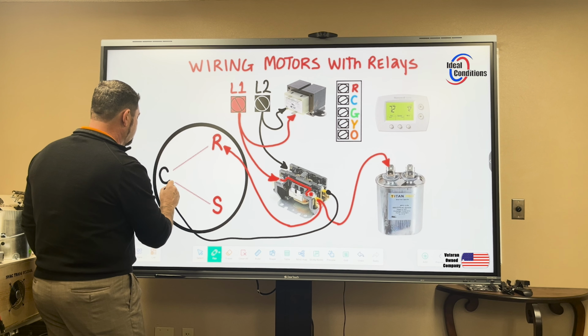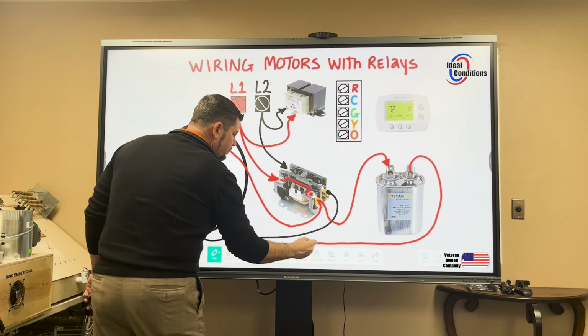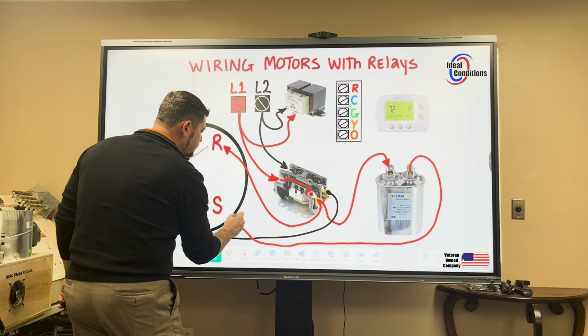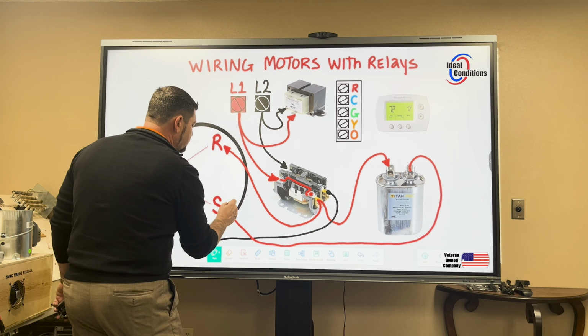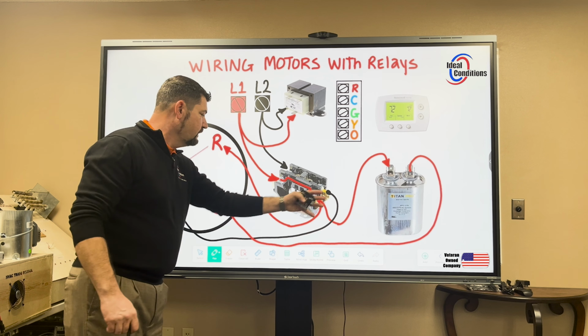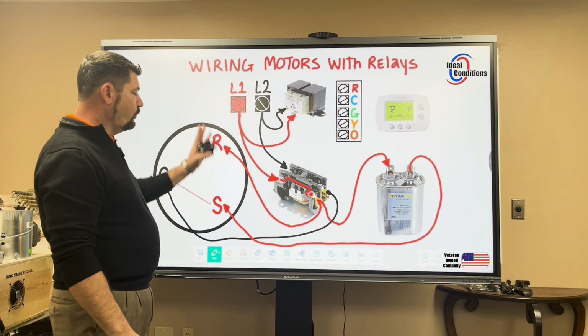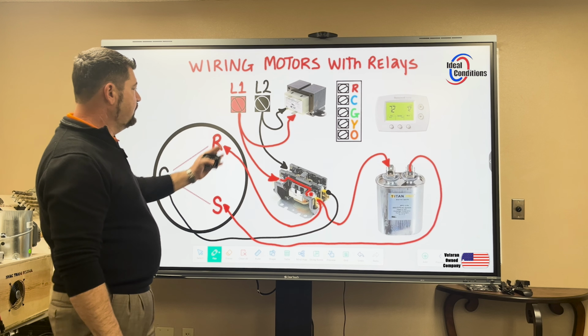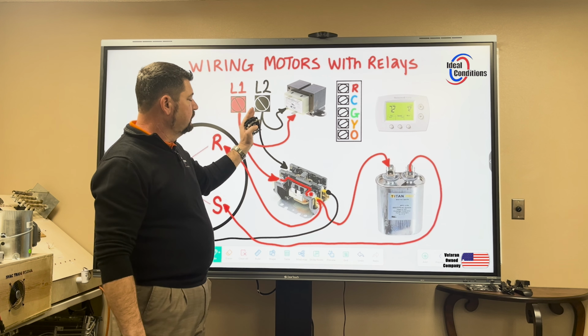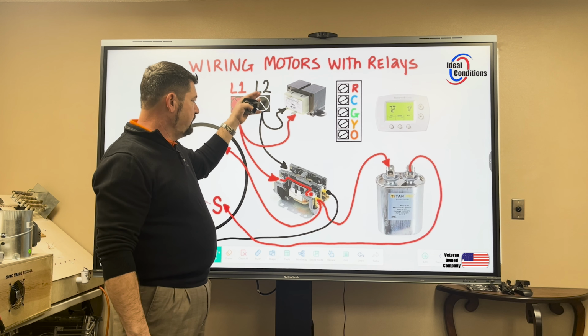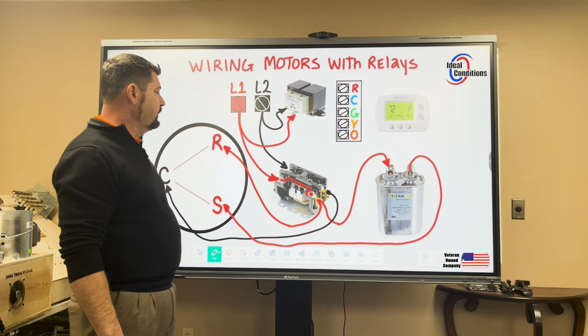Now, to complete the start winding circuit, L1 comes out of the capacitor and comes over to start. Notice that run and start are on the same leg. So everything has been color-coded red at this point in time that is on one leg of power, and everything has been color-coded on the same leg for the other leg of power.